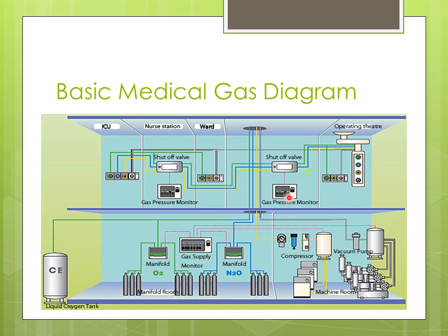One thing I want to bring note to is that if you look at this line right here, this is like the room wall, this gray line going up and down. And you'll notice that your gas monitor is outside the room, and your shutoff valves, as well as things you will run into later as we talk about gas and medical gases, about location of shutoff valves and monitors.